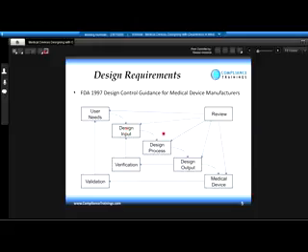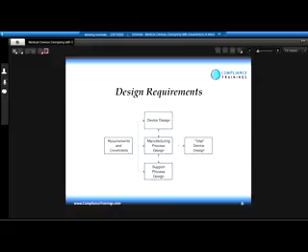You look at your user needs, which feed into your design input, your design process, and design output, which has to be verified to make sure that the output and the input are falling into place. And then you produce a medical device which needs to go through a validation to make sure it meets user needs. And of course, every step in the process has a review.